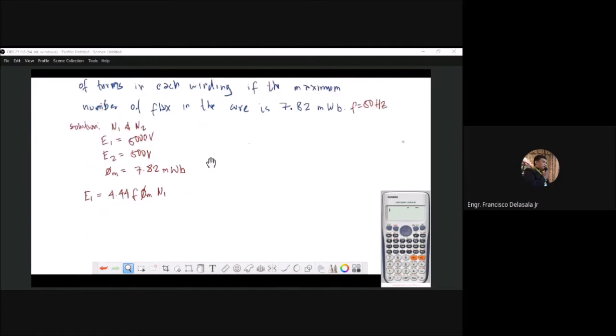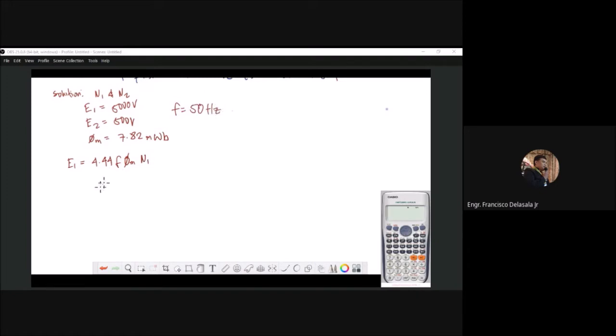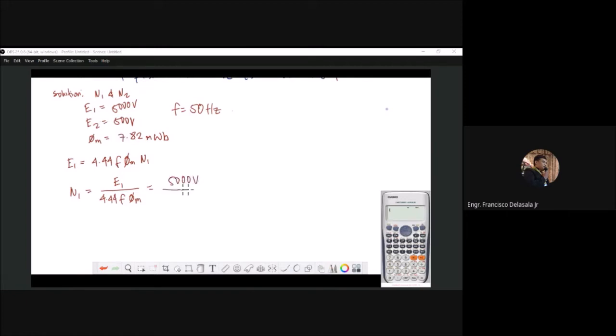So f is equal to 50 Hz. Solving for N1, we have N1 = E1 / (4.44 × f × φ_m). From the given, E1 is 5000 volts, frequency is 50 Hz, and φ_m is 7.82 milli-Weber.